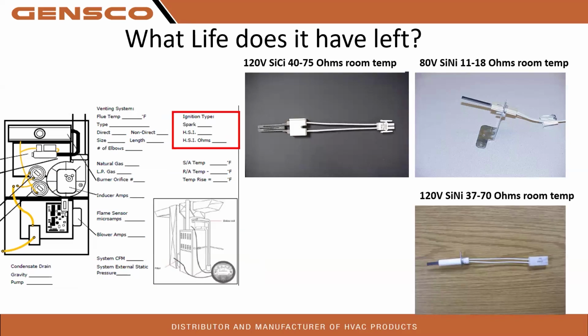Okay, also too, type of ignition: is it a spark? Is it hot surface igniter? Most all of our Trane stuff, other than commercial maybe, is going to be hot surface, whether it's carbide that you see here. You see how we also have nitrides, right? So we did run 80 volts for quite a while in the older models. We're pretty much out of the 80 volt market, but there's still enough of them out there. We've had them for years. Then we have the 120 volt that we're using in all of our gear these days.